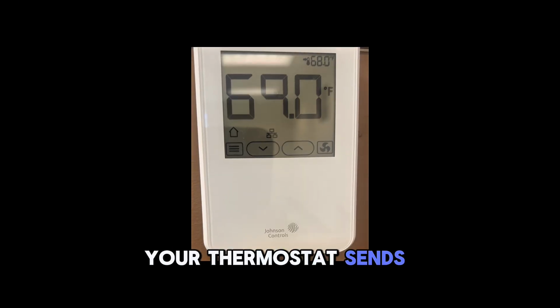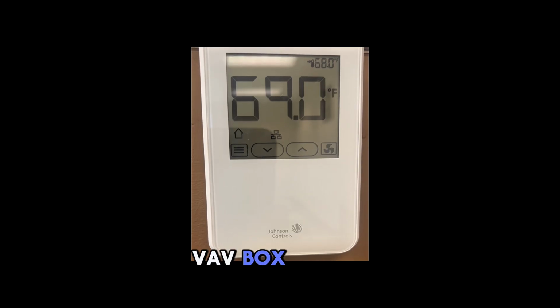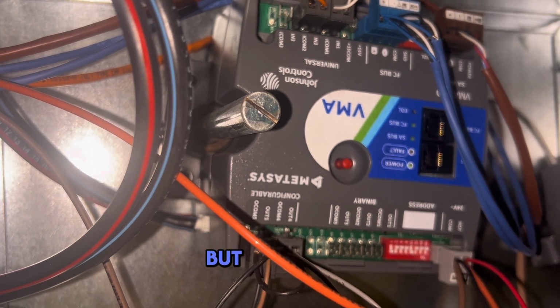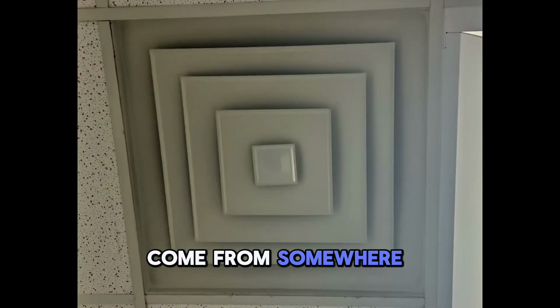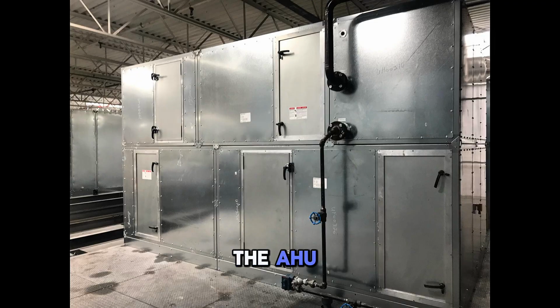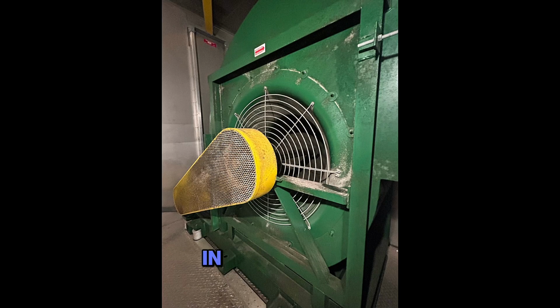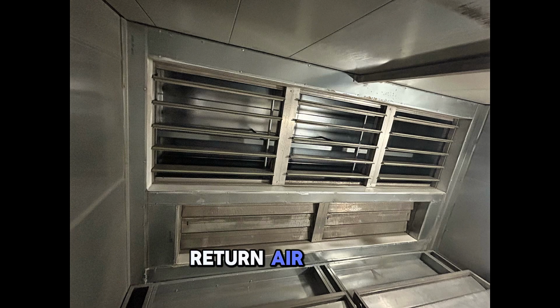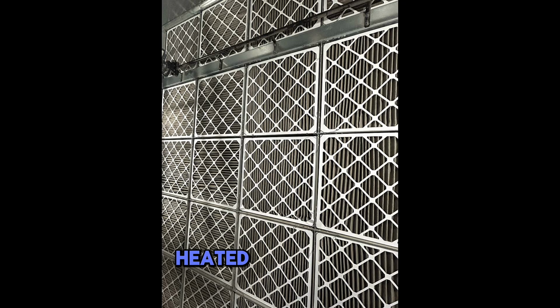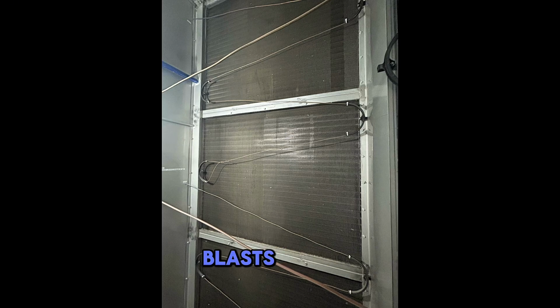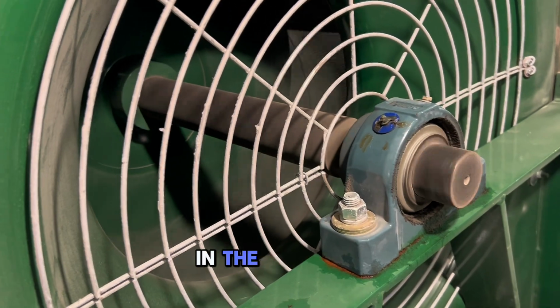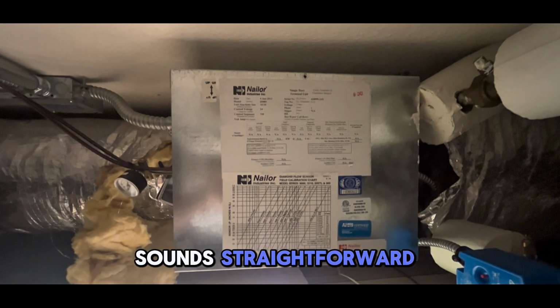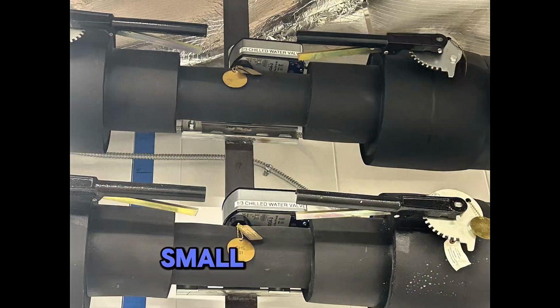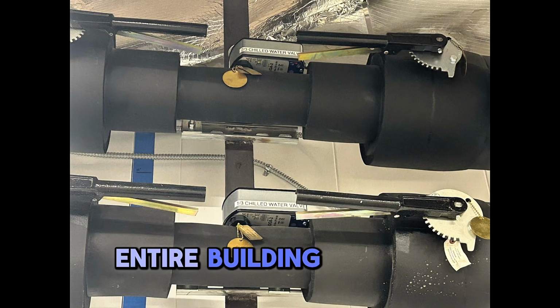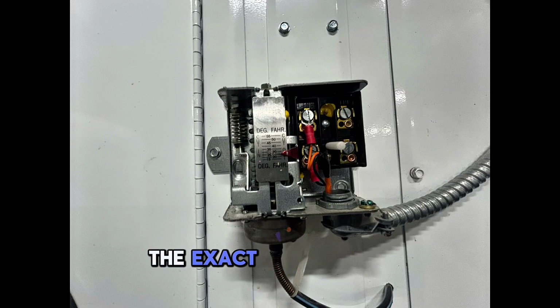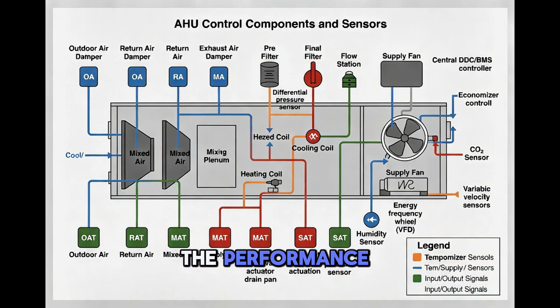Your thermostat sends a signal, the VAV box opens or closes. But all that air has to come from somewhere. That somewhere is the AHU. Outside air comes in, mixes with return air, gets cleaned, heated or cooled, then the fan blasts it out to every VAV in the building. Sounds straightforward. But when one small thing goes wrong here, the entire building suffers. I'll show you the exact components and what kills the performance.